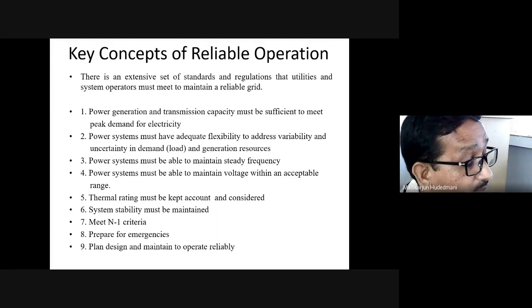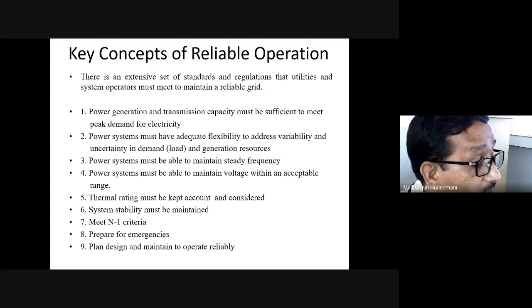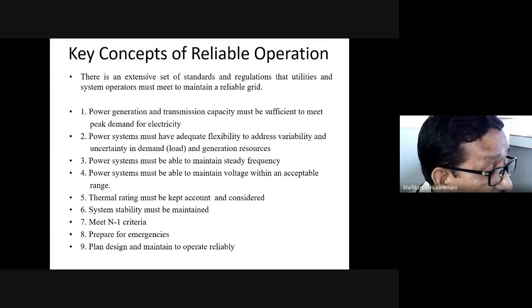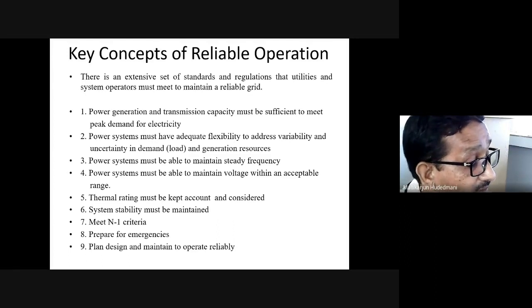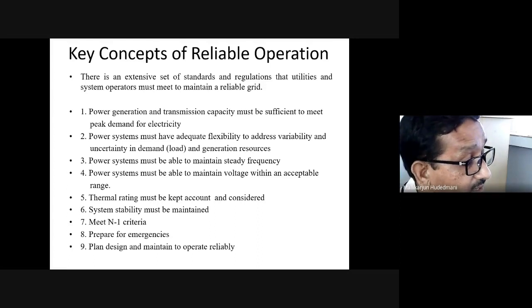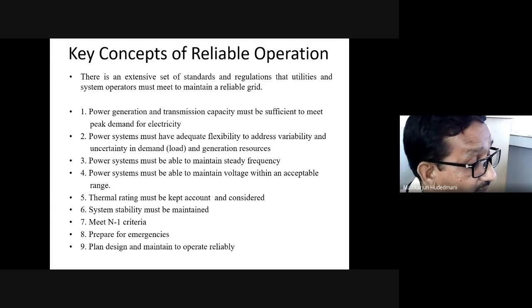Now you can look forward. This can be one of the important steps for assessment of the security and reliability of the system. So it need not be N-1, it can be N-2, it can be N-3. It means if two components of the interconnected N components fail and two are not there for service, the remaining system is in there. How is it going to behave? Its performance, its reliability, its adequacy at that delivery of power.